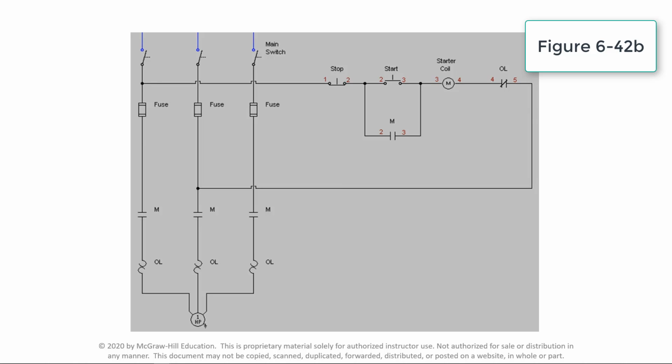This video demonstrates the operation of a thermal overload relay circuit with automatic reset only. The operating principle is basically the same as the manual reset only. The difference being, with automatic reset, after the heater element cools, the system will be automatically restarted.